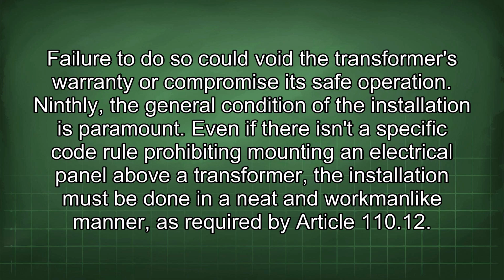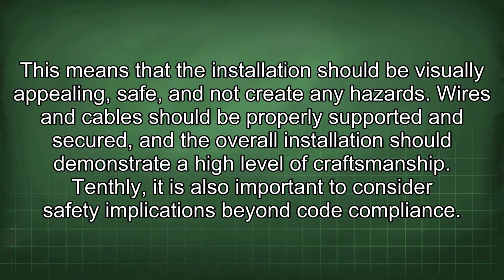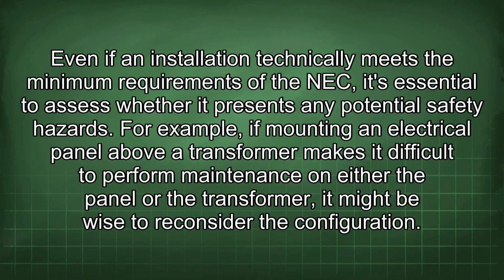Ninthly, the general condition of the installation is paramount. Even if there isn't a specific code rule prohibiting mounting an electrical panel above a transformer, the installation must be done in a neat and workmanlike manner, as required by Article 110.12. This means that the installation should be visually appealing, safe, and not create any hazards. Wires and cables should be properly supported and secured, and the overall installation should demonstrate a high level of craftsmanship. Tenthly, it is also important to consider safety implications beyond code compliance. Even if an installation technically meets the minimum requirements of the NEC, it's essential to assess whether it presents any potential safety hazards. For example, if mounting an electrical panel above a transformer makes it difficult to perform maintenance on either the panel or the transformer, it might be wise to reconsider the configuration.